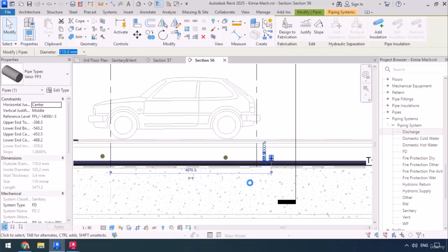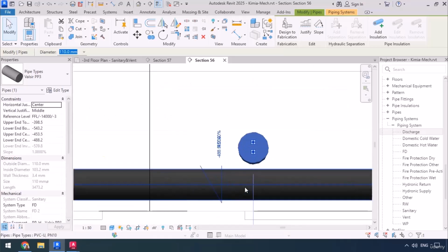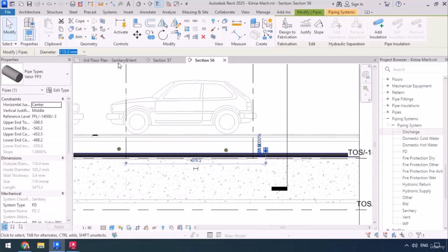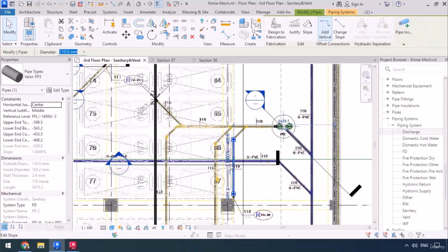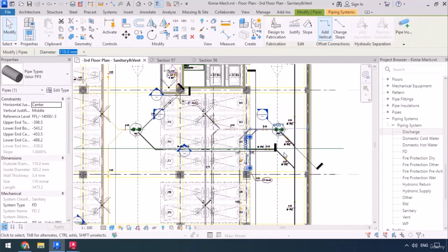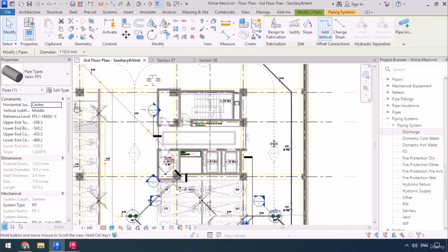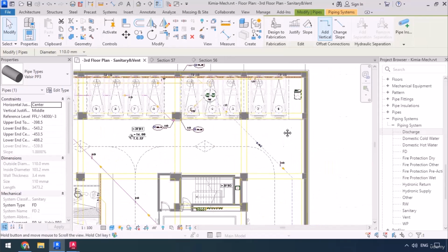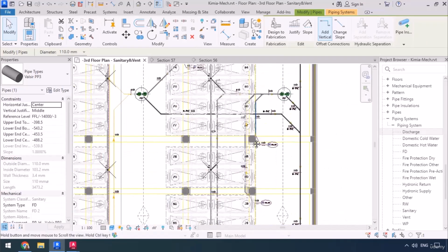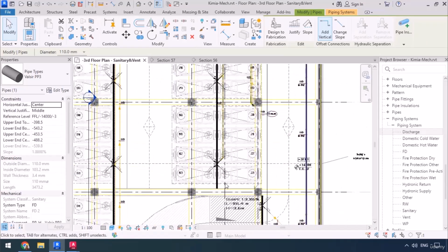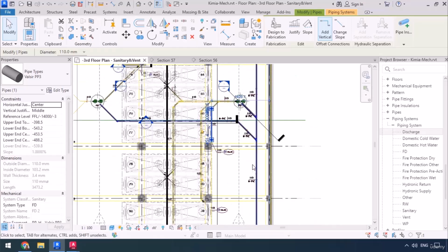So if I move one of them up, all of them will go up because they're all connected to each other. And also that interference we had was at the ends. But again, there might be some pipes over here interfering with this pipe or any others. But for now, for this pipe, which is lengthier and doesn't have any slope, we try to keep it as close as possible to the floor. And instead of repositioning that, we raise some of these sloped pipes higher.